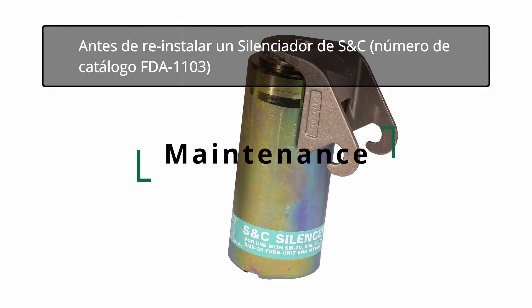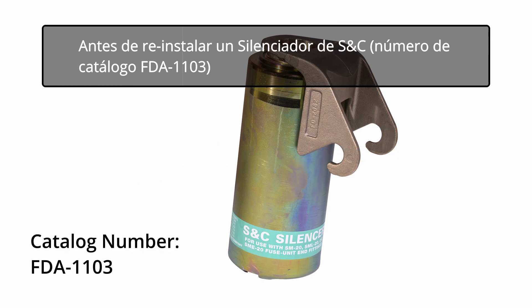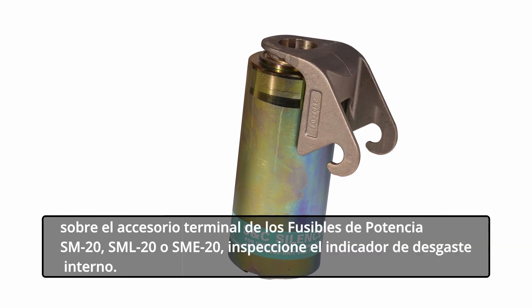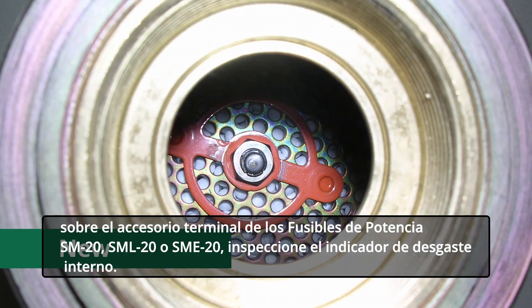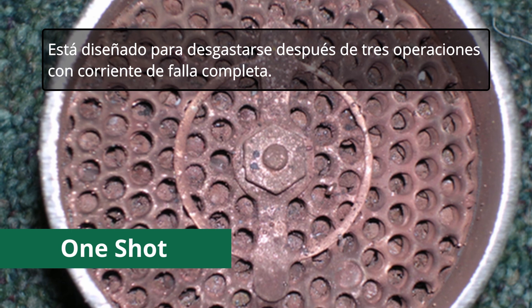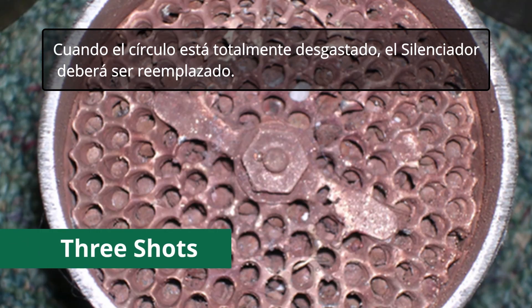Before reinstalling a previously used S&C silencer, catalog number FDA-1103, manufactured after June of 2007, onto the end fitting of the SM20, SML20, or SME20 power fuses, inspect the internal wear indicator. The indicator is a red metal ring mounted on the bottom of the open chamber of the silencer, and will erode with each fuse operation. It is designed to be worn away after three operations at full fault current. When the circle is completely worn away, the silencer should be replaced.